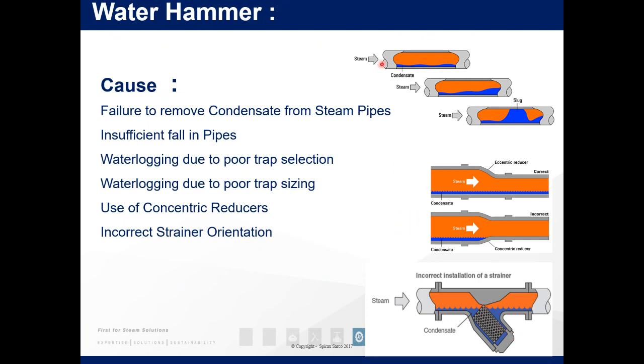So I'll start from the top. When we have water hammer, effectively we have water in the line. As the steam moves over the surface of that water, it picks up speed. There's a friction that goes on there picking up the water. That over time will produce a slug. You have steam that builds up behind it, which then pushes this slug down the pipe, and then you'll hear the bang where it hits a bend or a closed isolation valve or a piece of equipment. So that's how water hammer is forming and where the sound is coming from.